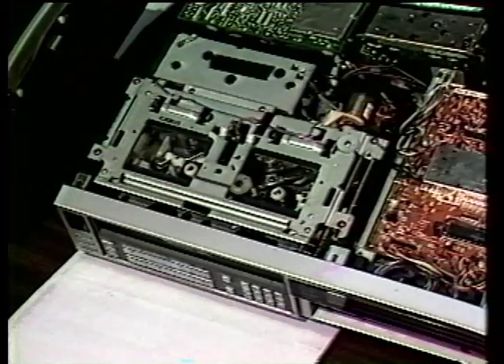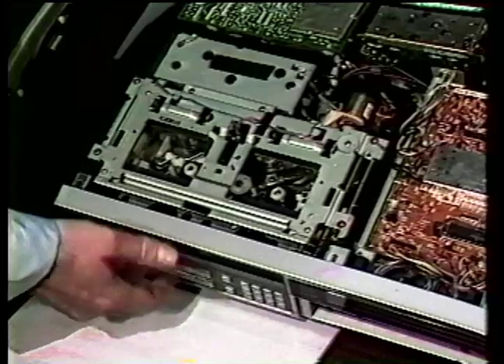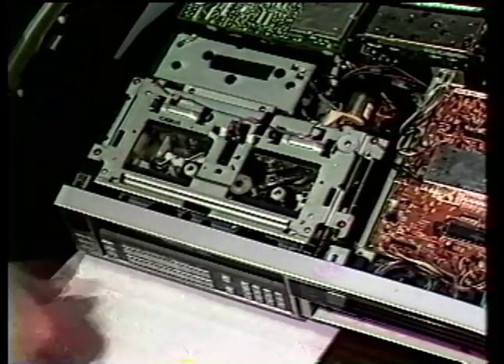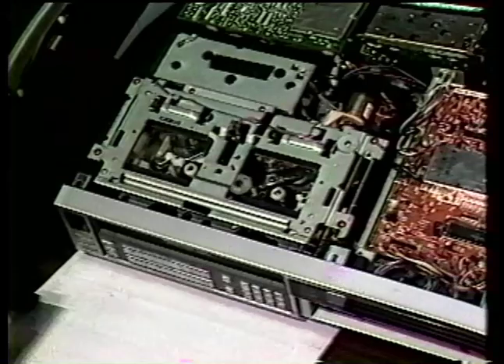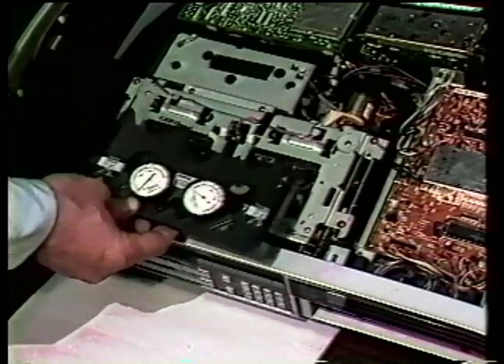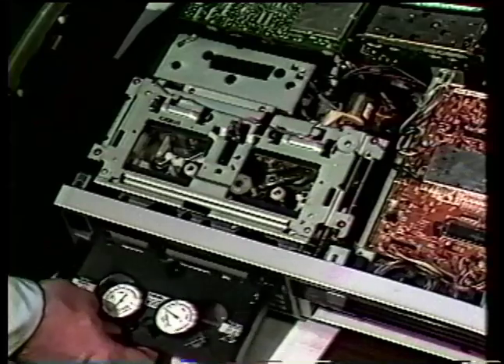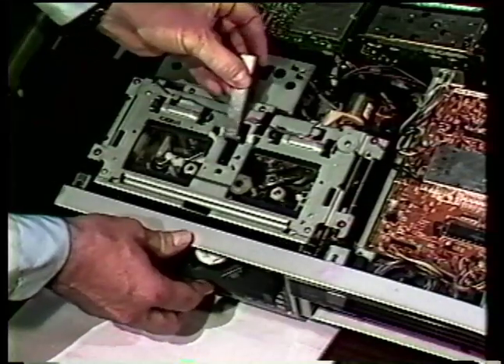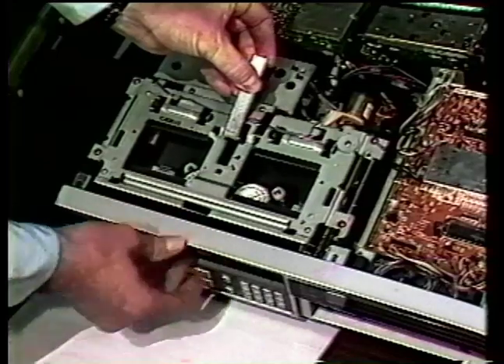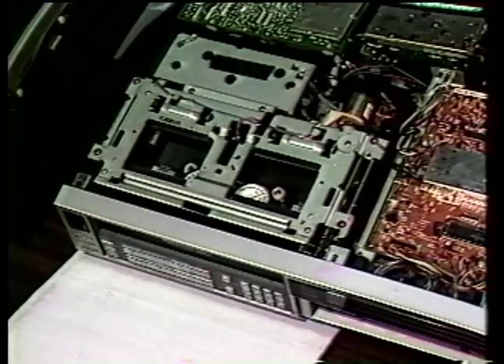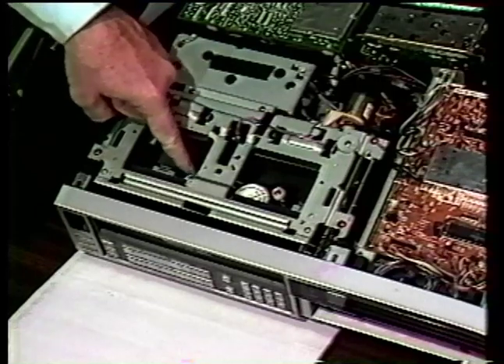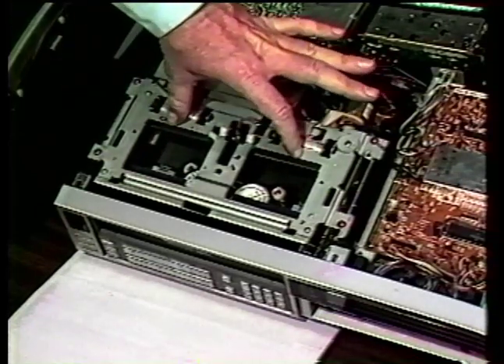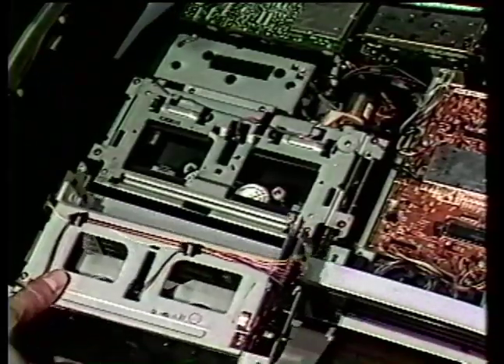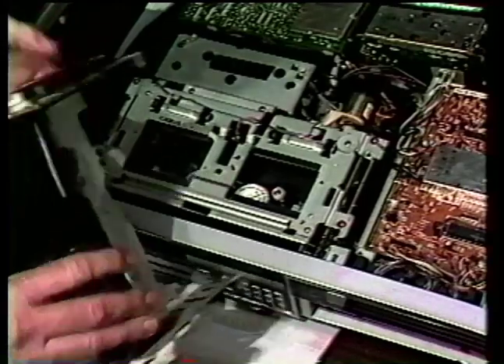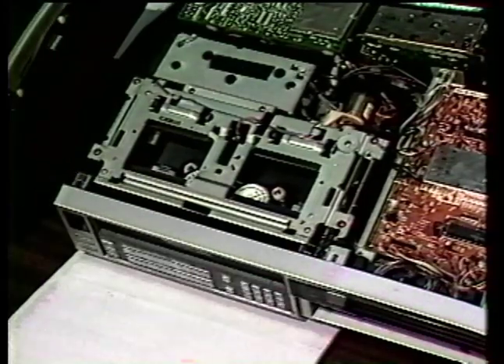Another variation worth mentioning, some front-loading machines have a switch in the center position so that the cassette energizes that switch when it goes in. Since the spindle height gauge has no solid area, it's necessary to just short out that switch so that you can load it in like a cassette. Once loaded, you can read the indicators directly through the carriage assembly, which saves an awful lot of time. Most manufacturers' methods have you pull the carriage assembly out of the machine, which is quite an operation.